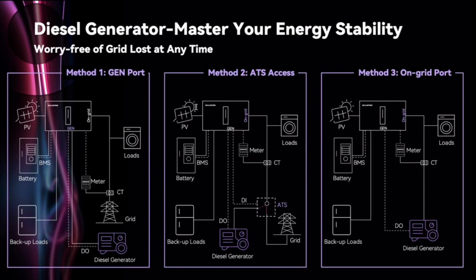And if the generator itself doesn't support the dry control, you can also get a DG controller from the market to achieve the same effect. And this setup can work both on-grid and off-grid, and it can also support battery charging for the backup power. The second method is to connect through the ATS, the automatic transfer switch. And in this case, the grid will act as the main power source, and the diesel generator will work as an auxiliary source. So when the grid goes down, the ATS will automatically switch the supply to the generator, ensuring continuous power for your loads.